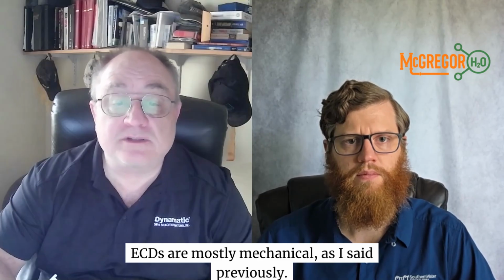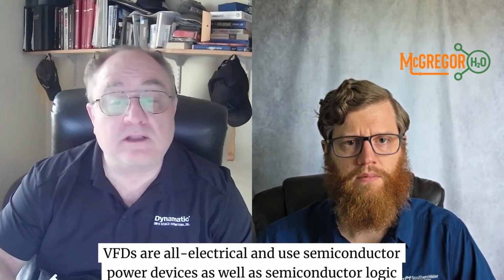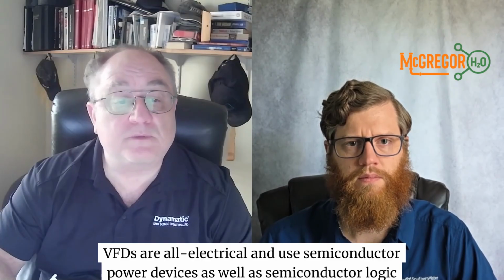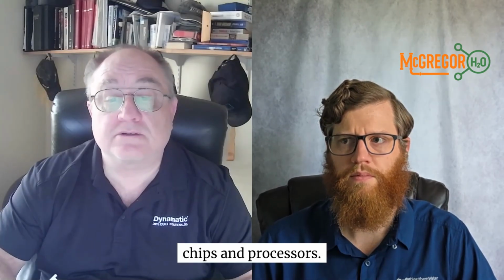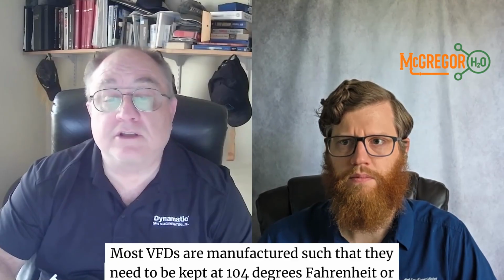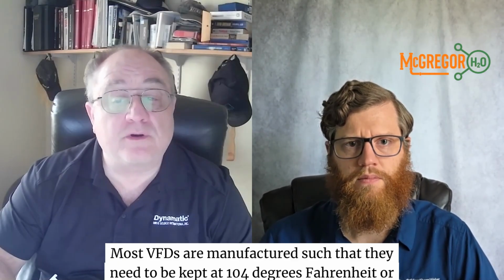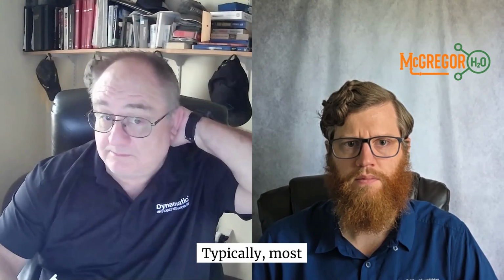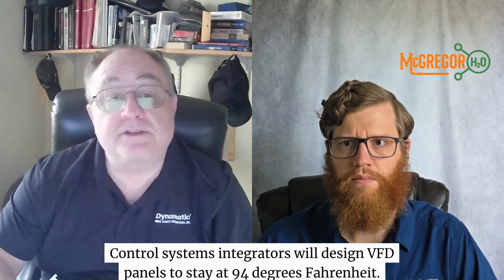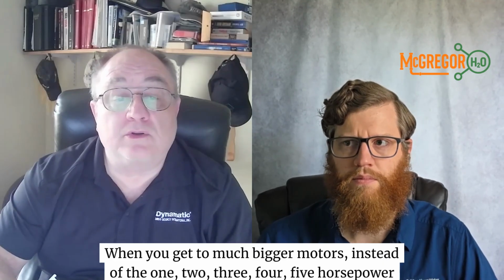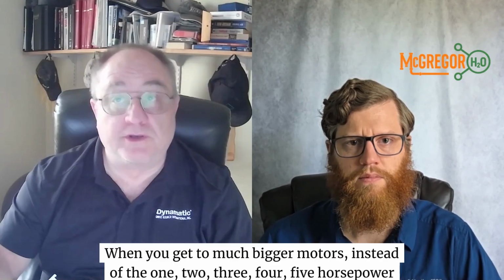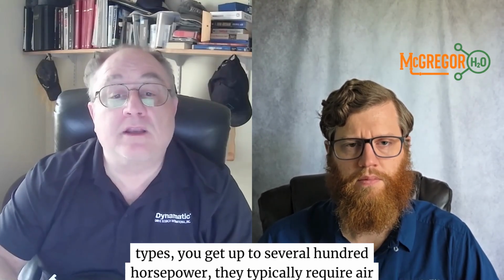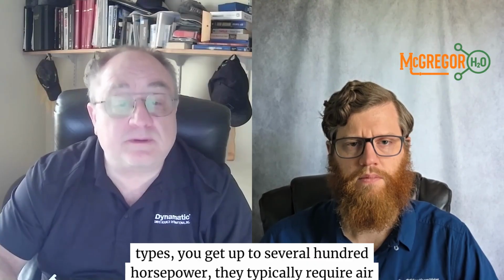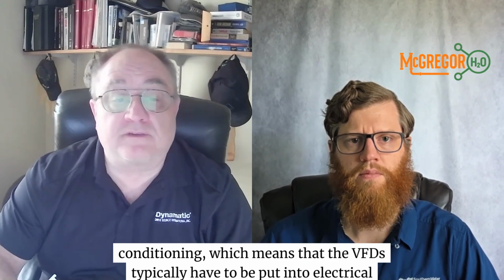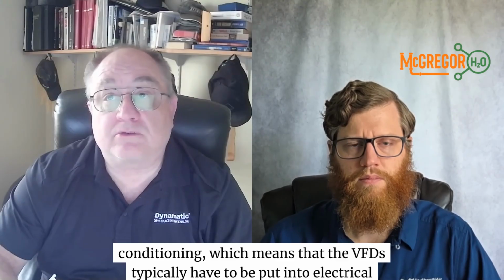ECDs are mostly mechanical, as I said previously. VFDs are all electrical and use semiconductor power devices as well as semiconductor logic chips and processors. Most VFDs are manufactured such that they need to be kept at 104 degrees Fahrenheit or lower. Typically, most control systems integrators will design VFD panels to stay at 94 degrees Fahrenheit. When you get to much bigger motors, instead of the 1, 2, 3, 4, 5 horsepower types, you get up to several hundred horsepower, they typically require air conditioning, which means that the VFDs typically have to be put into electrical rooms that are cool.